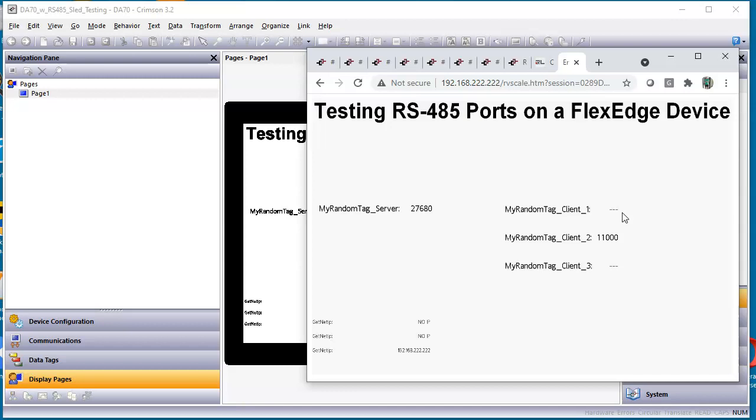By the way, when I'm not connected, right now I'm not connected, only the green LED is blinking on the first port that's set up as the Modbus master. Only the green LED is blinking. Once I plug it into the other, I get the green for receive traffic. And so now I can see the red and green on both, and it works great. So I've tested in this case that my 485 ports work great on all four of the ports I have. Very simple test.